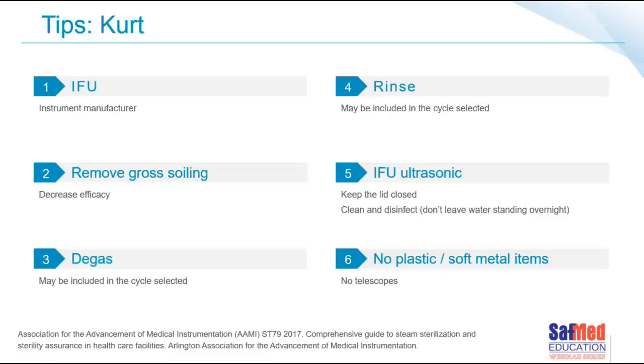The ultrasonic creates its own tiny bubbles, which will create the cavitation and clean the instruments correctly. And if there's extra gas in there, it will collide with these tiny bubbles, and of course reduce the efficacy of the cleaning. So gases in the water will actually affect the cleaning efficacy at the end of the day. That's correct. So if it's a manual unit, this is how it happens. If you are draining the water out during the day, every time you refill the manual unit with water, you will run an empty cycle, and that's technically your degas cycle. If it's an automated unit, it will have a degassing phase before the wash cycle.